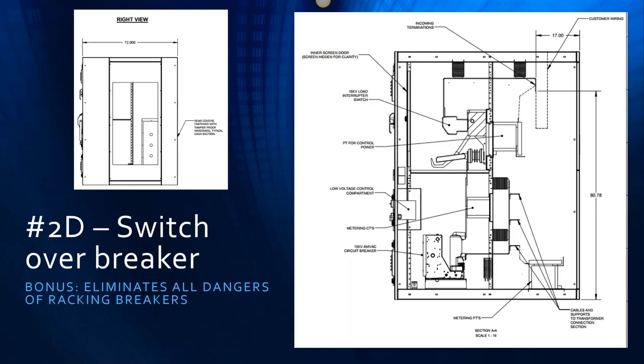So this has all the advantages I previously mentioned associated with the 3-position isolation switch, where whether you have a fixed mount breaker or a draw out breaker, you can isolate that breaker for maintenance purposes. And statistically speaking as well, you now have the option of avoiding racking, whether it's remote racking or racking right in front.